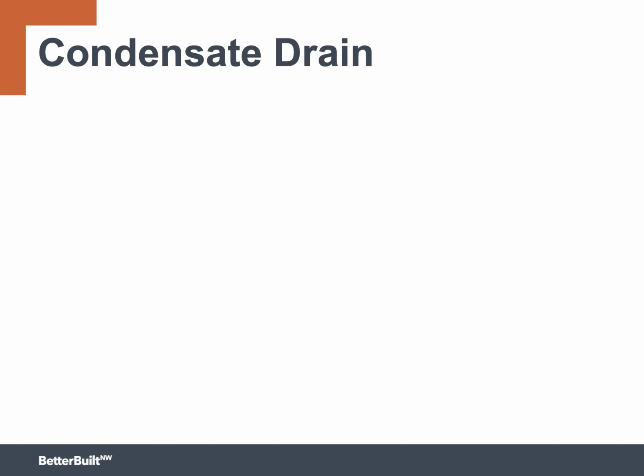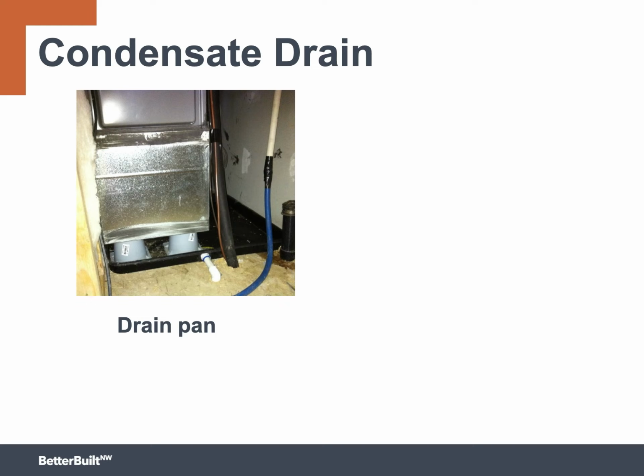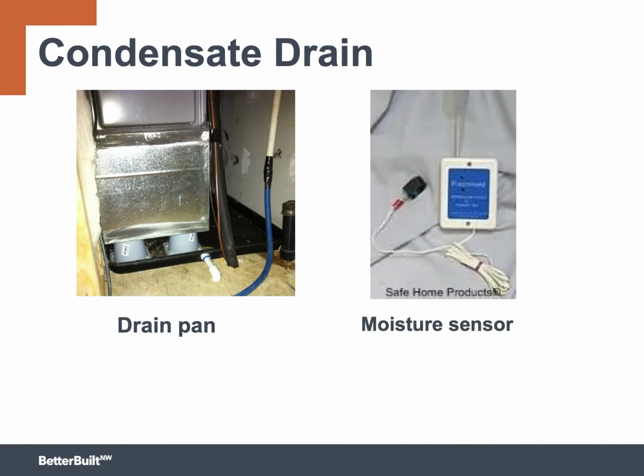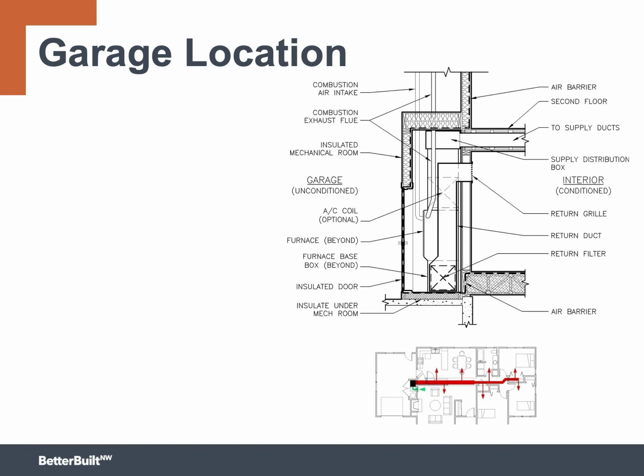High-efficiency furnaces have a drain line to carry condensate away from the combustion chamber and from the air conditioning coil. When the furnace is located inside the conditioned space, you have to protect yourself from possible problems with the condensate. Most people also want to see a second layer of protection with a drain pan underneath the air handler. This is probably the best way to go. Some builders use moisture sensors with an alarm that goes off whenever moisture is present in order to bring people's attention to the fact that there could be an overflow or a leak.